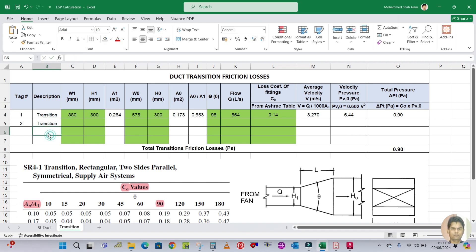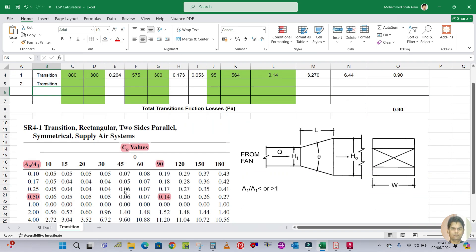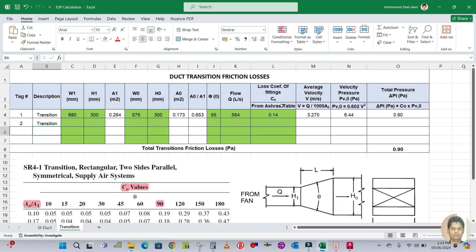If there is another transition piece, you can continue the same process - enter the serial number, transition description, width one, height one, width zero, height zero, get A0/A1 from the table, enter theta and the Co value, and the Excel program will automatically calculate the pressure drop. I hope you have learned how to calculate pressure drop for a transition piece. Please subscribe, like, and share the video. Thank you.